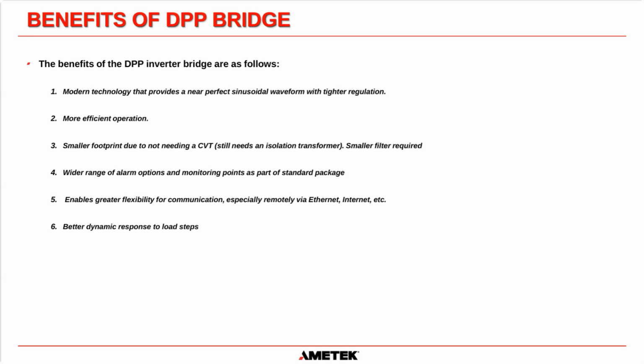And lastly, the DPP has better dynamic response to load steps, which I mentioned earlier. If you slam a load onto a DPP system, it's going to react very quickly. It's going to widen all of those pulses in real time. And the dynamic response, in other words, how the voltage dips when you put on that load, it will be much less than a DSC system.